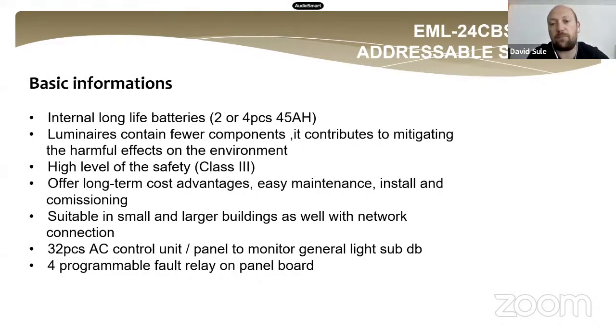The next big advantage of the DC 24 volt system against the AC 230 system is the cabling. In the AC 230 system, we can use only a straight line, with the luminaires connected one by one. But here, with DC 24 volts, any type of junction and any type of cabling route are available. So you can reduce the cable length by using junction boxes, and you can spread the cables in multiple ways.